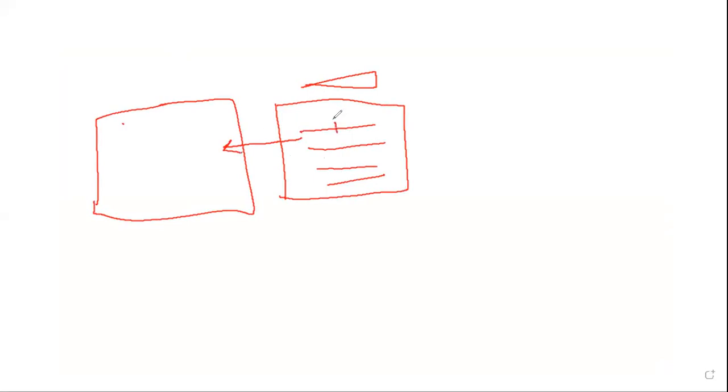So this little slider controls let's say the upper sector, and this one controls the sector below, and this one controls the sector below, and so forth. So the TGC does what? It controls the brightness, but in sectors, in every part of the image. This allows you to control your gain in every part of the image.